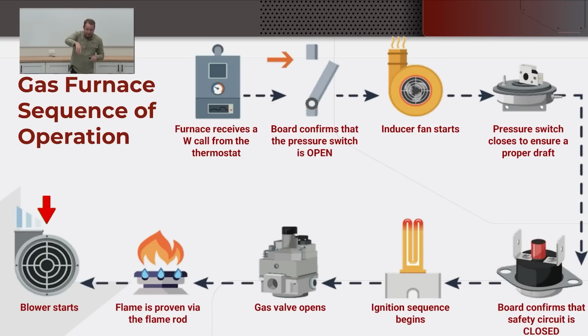If it's nice and stable, blower goes on and it really starts moving on you, that's an indication that you have leakage in between those two air streams, your combustion air which is for the burner, and your blower which is down below.